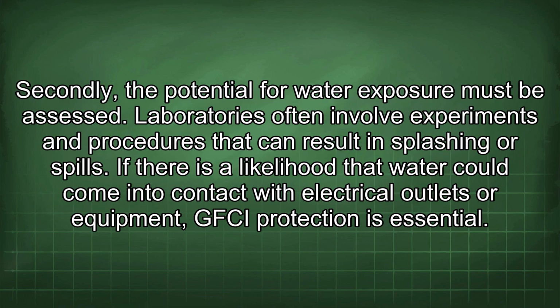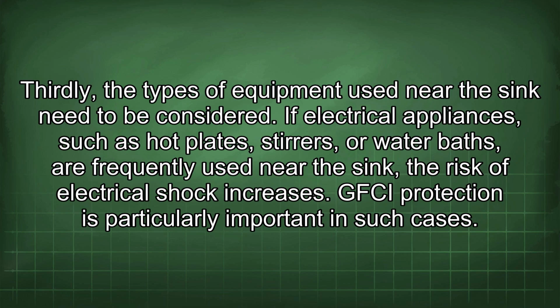Secondly, the potential for water exposure must be assessed. Laboratories often involve experiments and procedures that can result in splashing or spills. If there is a likelihood that water could come into contact with electrical outlets or equipment, GFCI protection is essential. Thirdly, the types of equipment used near the sink need to be considered. If electrical appliances, such as hot plates, stirrers, or water baths, are frequently used near the sink, the risk of electrical shock increases. GFCI protection is particularly important in such cases.